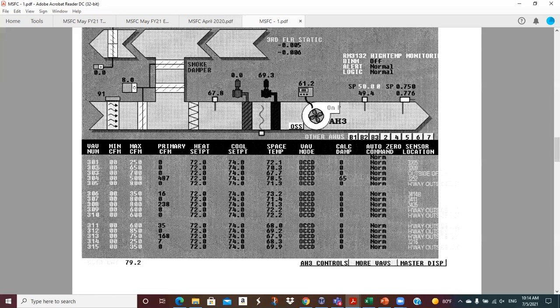So on this unit, these I think are VAV box numbers. It says minimum CFM of 0, but I find that hard to believe that these things would go to shut off, because that's for ventilation. They usually don't let them go to shut off. Primary CFM. So, I don't know. I'm not sure how they've got this.